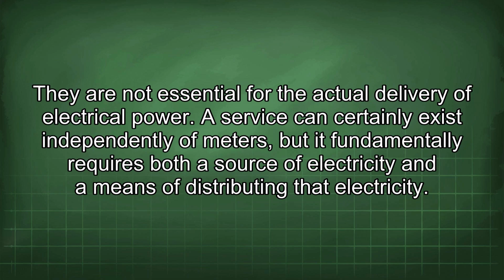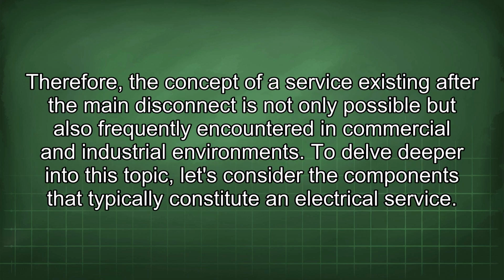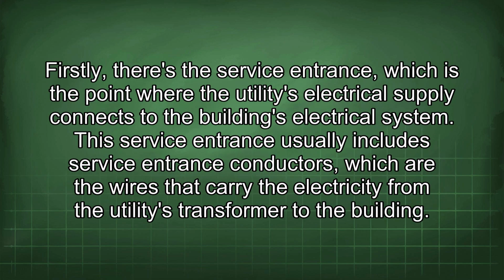A service can certainly exist independently of meters, but it fundamentally requires both the source of electricity and a means of distributing that electricity. Therefore, the concept of a service existing after the main disconnect is not only possible but also frequently encountered in commercial and industrial environments. To delve deeper into this topic, let's consider the components that typically constitute an electrical service. Firstly, there's the service entrance, which is the point where the utility's electrical supply connects to the building's electrical system.